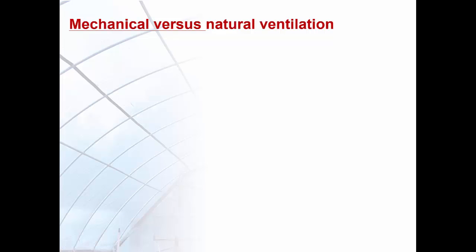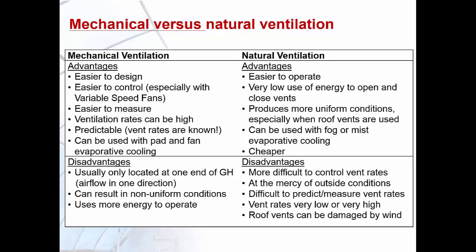There are advantages and disadvantages to both mechanical and natural ventilation systems. Advantages of mechanical ventilation include being easier to design and control, especially with variable speed fans. Ventilation rates are predictable and easier to measure. High ventilation rates can be achieved, and mechanical systems can be combined with pad and fan evaporative cooling. A disadvantage is that fans are usually located at one end, creating airflow in one direction, leading to non-uniform conditions and higher energy use.